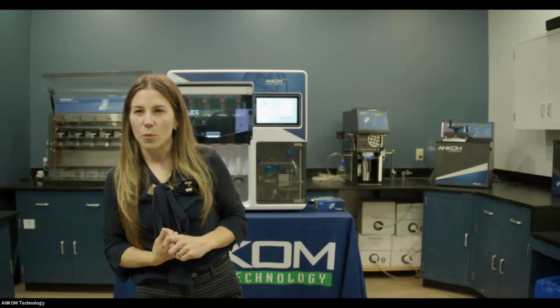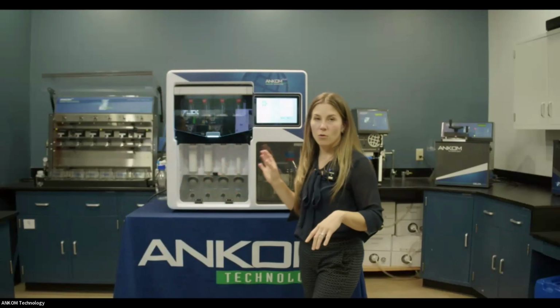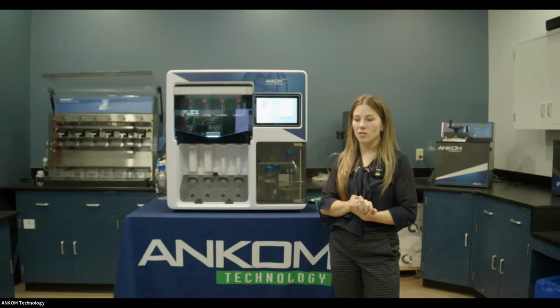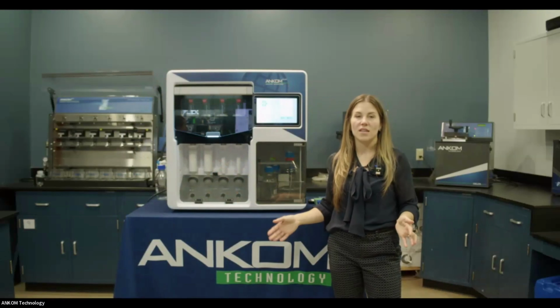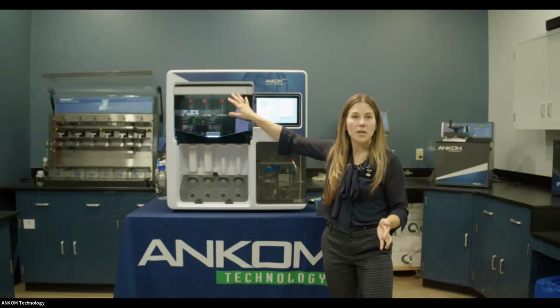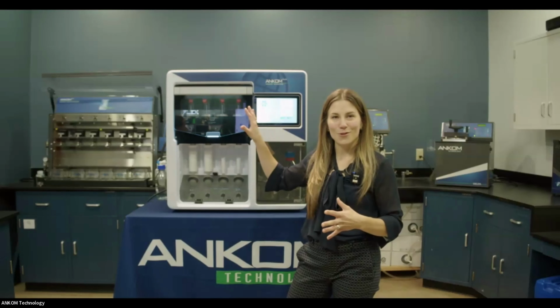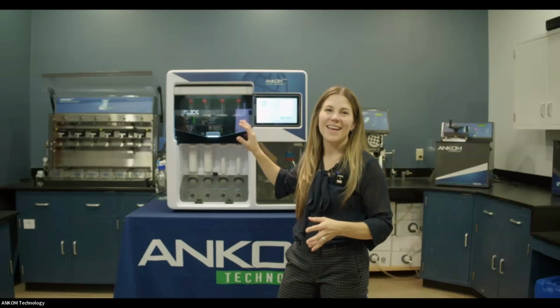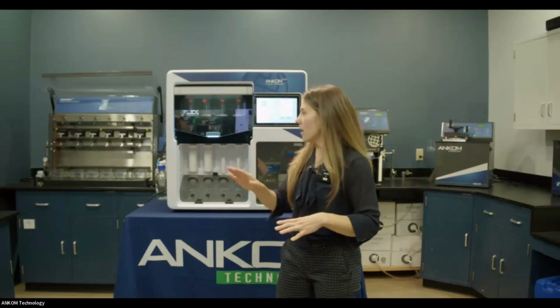How long from preparing the samples until you get the results? Great question. If you're talking about the Flex for total fat, your technician is going to take about 10 to 15 minutes to prepare their samples, put them in the digestion oven up here, and then press start and walk away. In about 2 hours, they will have their fat. If you're doing a vitamin analysis, they will put their samples in the digestion oven, press start, and walk away. In about 2.5 hours, they will have their vitamins. In one run and one position, you will get analyte that you can analyze for all vitamins, so A, E, D, and also cholesterol. You don't need to do those separately.